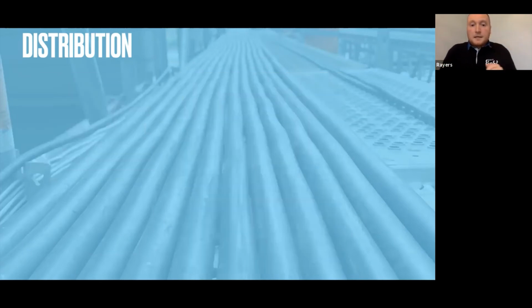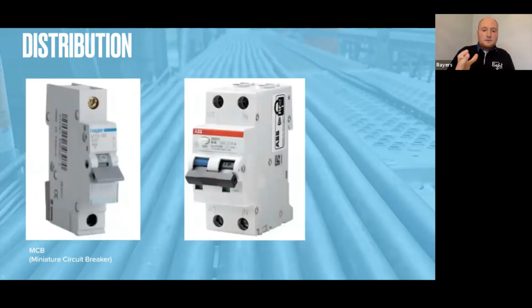It's imperative that when we use distribution boards we have adequate circuit protection, through MCBs and RCBOs. MCBs protect the equipment from melting the cable or distribution equipment. RCBOs protect people, and you can recognize those by the little test button below the red line, meaning it has some form of RCD protection. That doesn't necessarily mean it's fitted for personal protection, which is 30 milliamp protection for people. We should always ensure final circuits have 30 milliamp protection to protect people. So MCBs protect equipment, RCDs and RCBOs protect people.